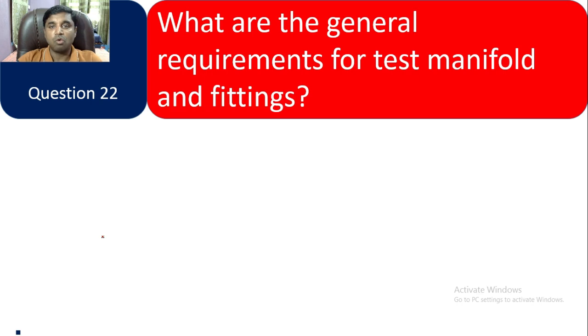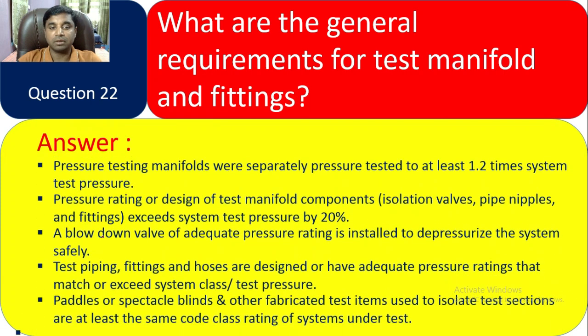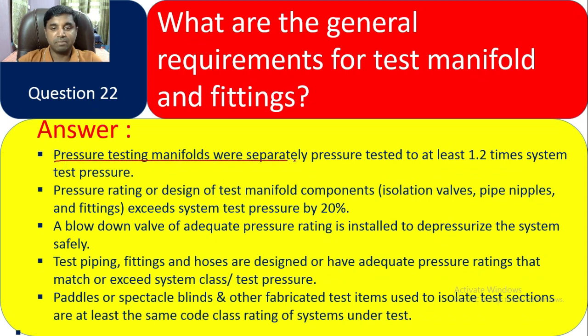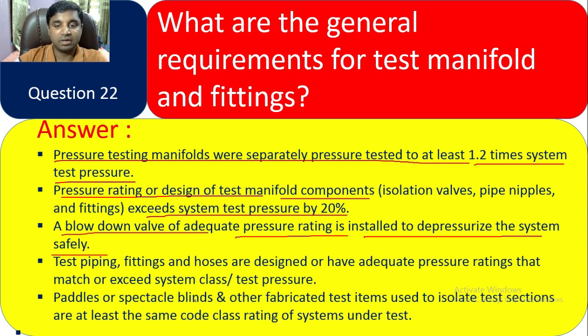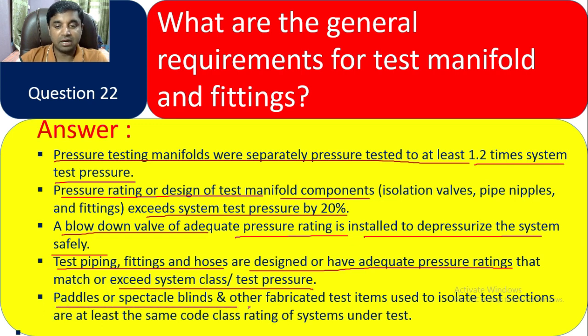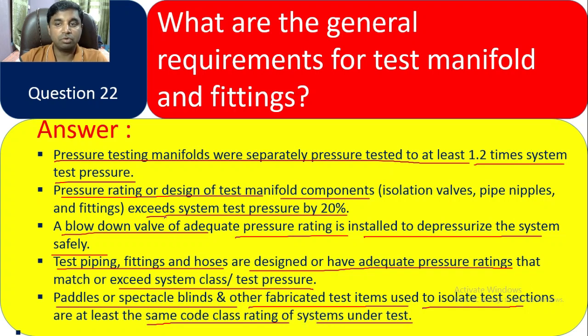Question 22: What are the general requirements for test manifolds and fittings? The manifold shall be separately pressure tested at least 1.2 times the test pressure. The design of test manifold components must exceed the system's test pressure by 20%. A blowdown valve of adequate pressure rating is installed to depressurize the system safely. Test piping, fittings, and hoses must have adequate pressure rating exceeding the system class test pressure. Paddles or spectacle blinds used to isolate the test section must meet the same code class rating as the system under test.